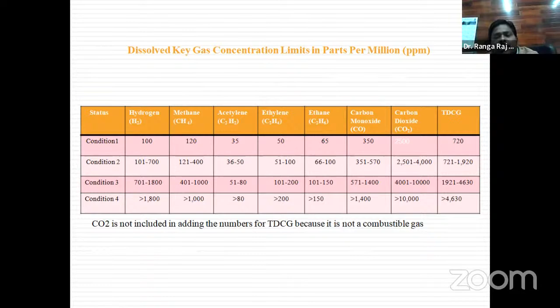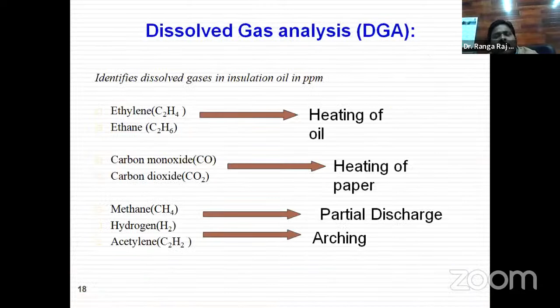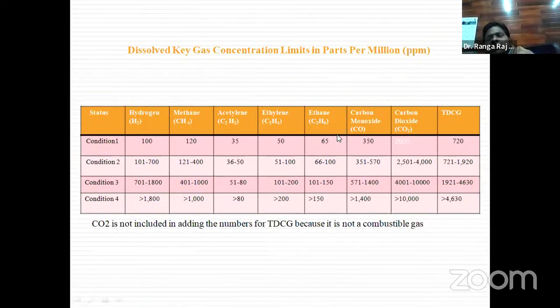There's no other option in the worst case. If it is in poor mode, we can dehydrate and filter the oil once or twice and use the same oil again. If it is good or excellent, there is no need to take any action. So with just this one DGA test, we can determine the various situations present inside the transformer as well as its overall health condition.